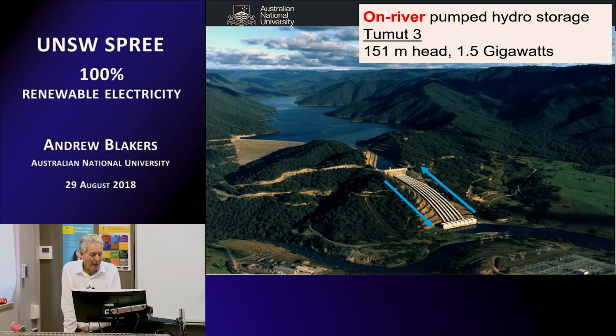The upper reservoir is actually the lower reservoir of the proposed Snowy 2.0 system, which connects that reservoir with Tantangara, with a head not of 150 metres but 650 metres. Head, the height difference, is very important because if you double the head, you double the power and energy, but you don't double the cost. That's why big heads are valuable.